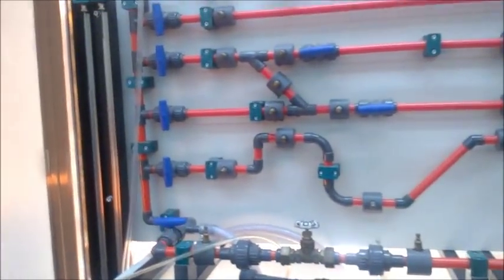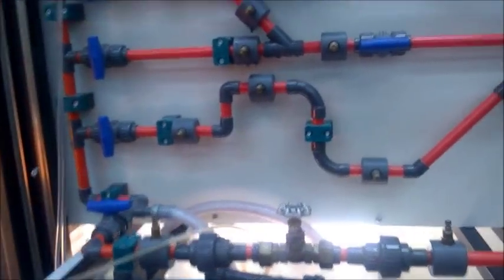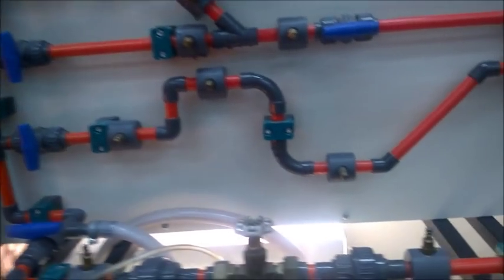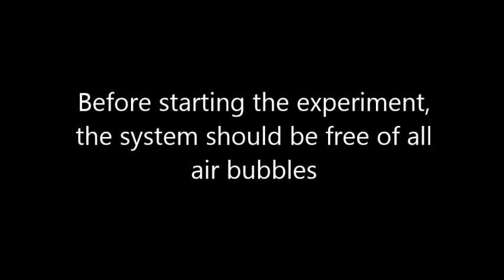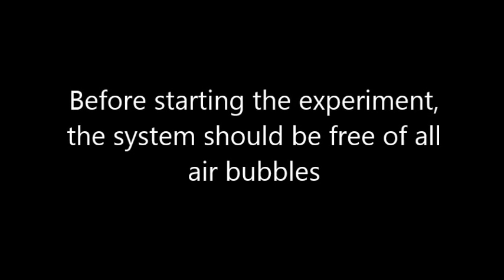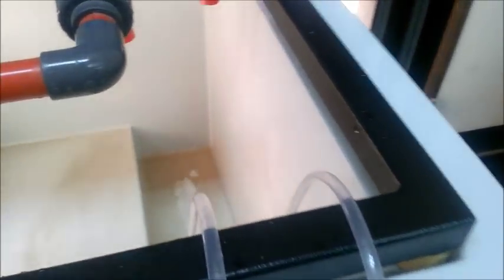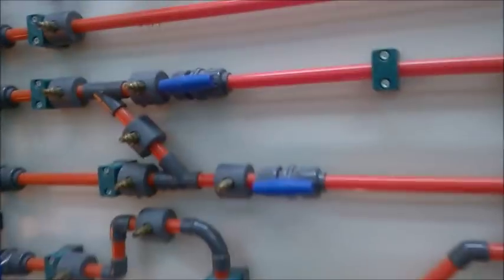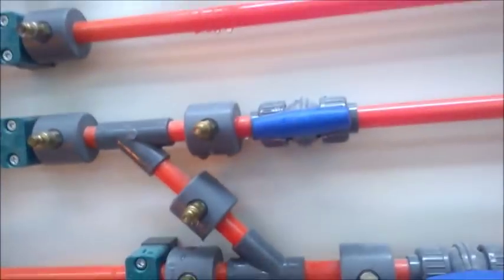We have to ensure that the system is free of all air bubbles. Now take the hoses of the manometers and connect them to the points in the pipe to measure the pressure drop.